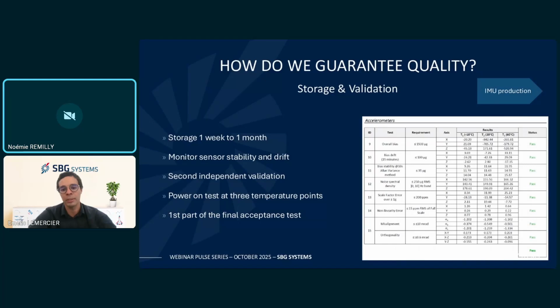We start from minus 10 degrees C, then 20 degrees C, and 60 degrees C. And we have power on of the IMU at all these 3 points, and then we evaluate the bias, the linearity, and also the alignment of our system. So this consists of the first part of the final acceptance test.